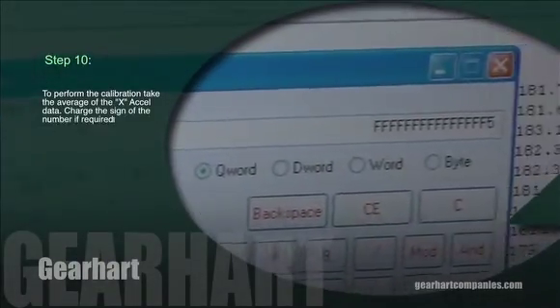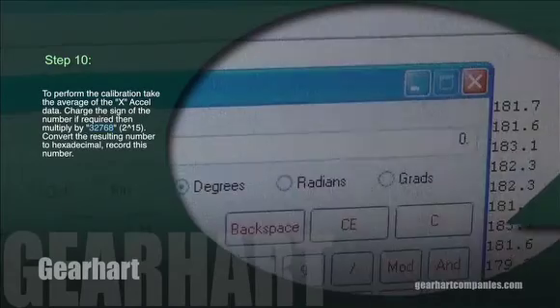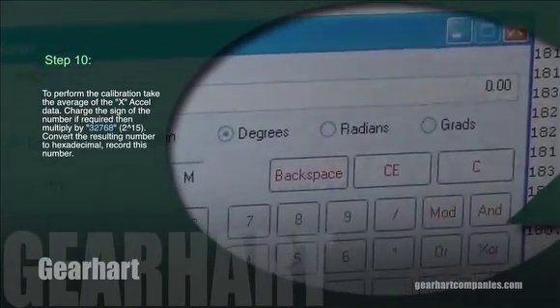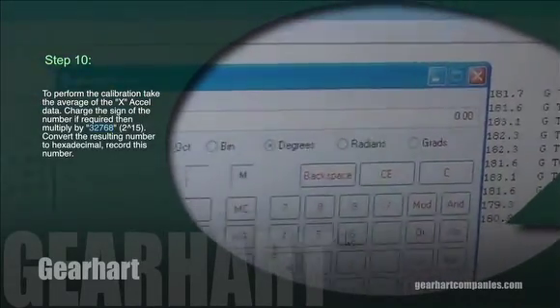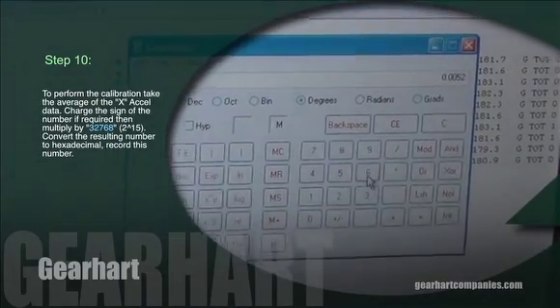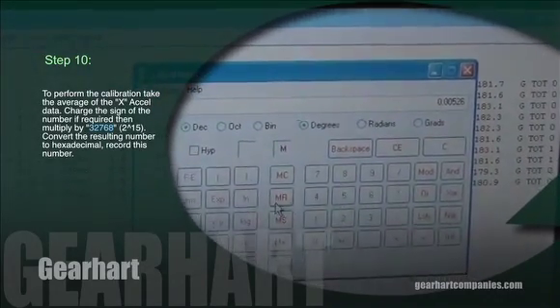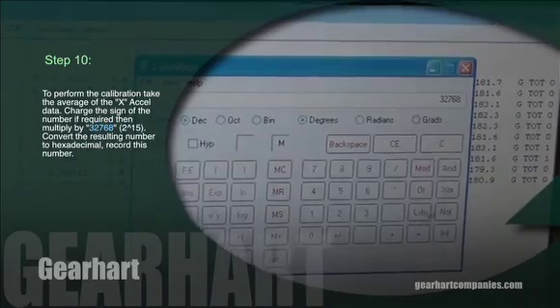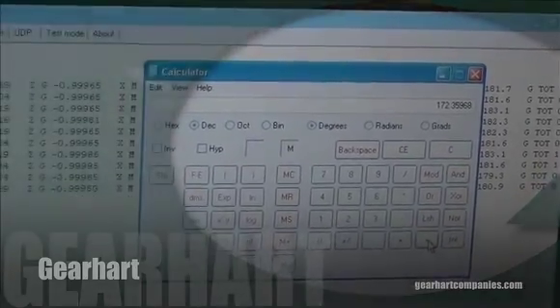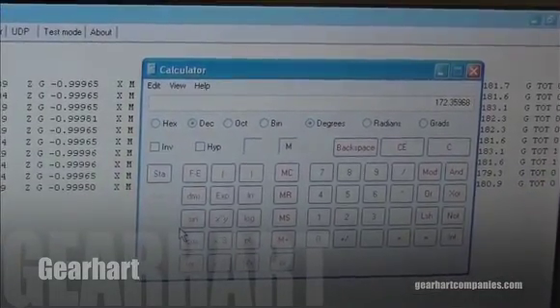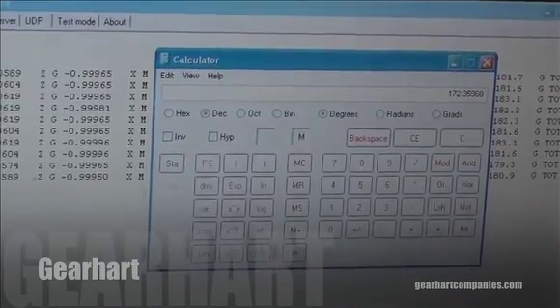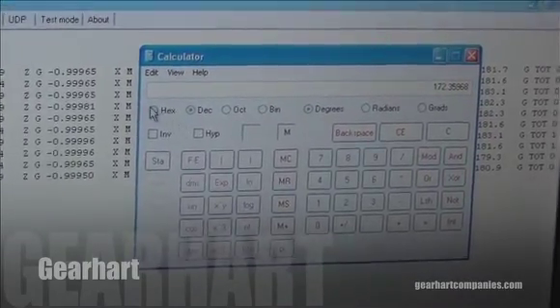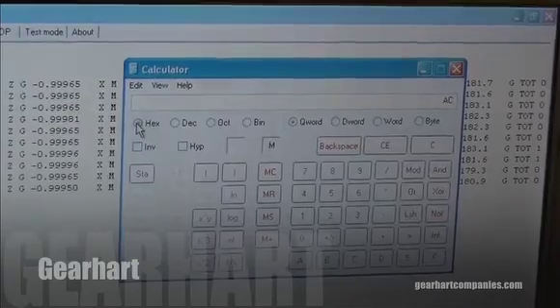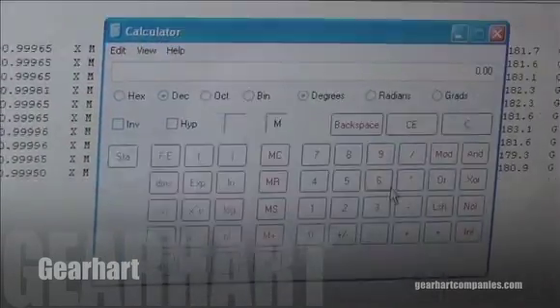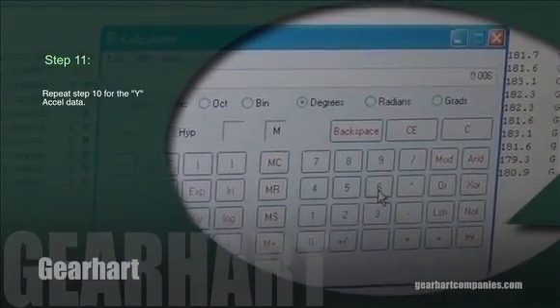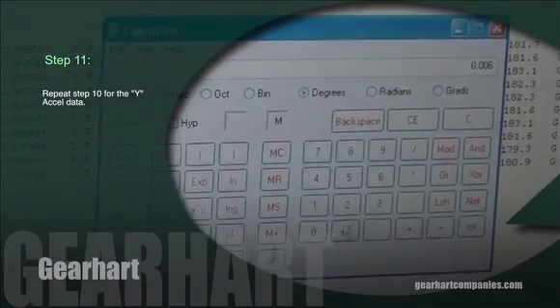Step 10. To perform the calibration, take the average of the accel data. Change the sign of the number if required, then multiply by 32,768, which is 2 to the 15th. Convert the resulting number to hexadecimal and record the number. Step 11. Repeat Step 10 for the Y accel data.